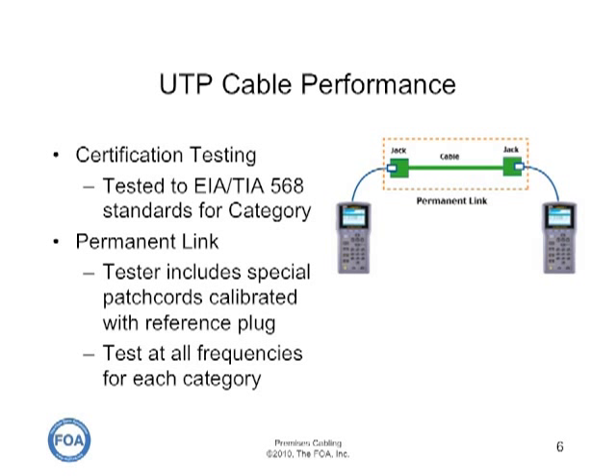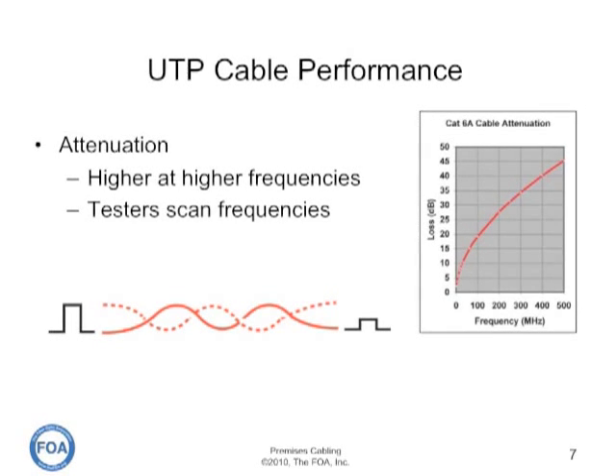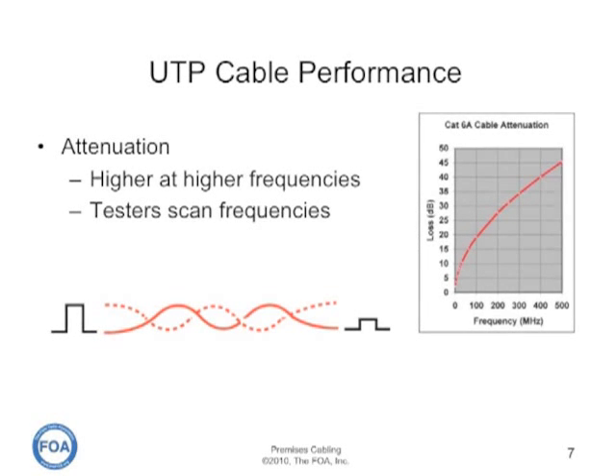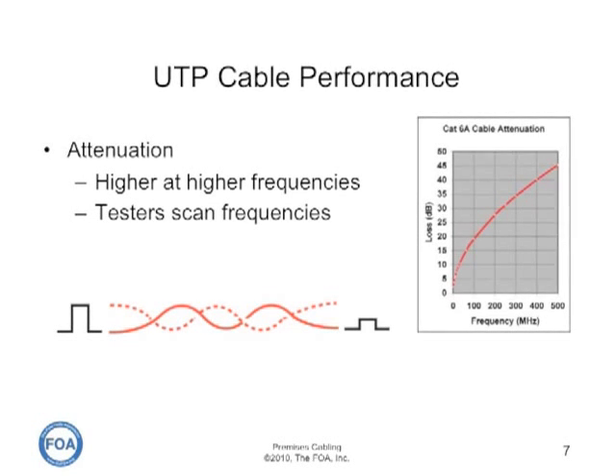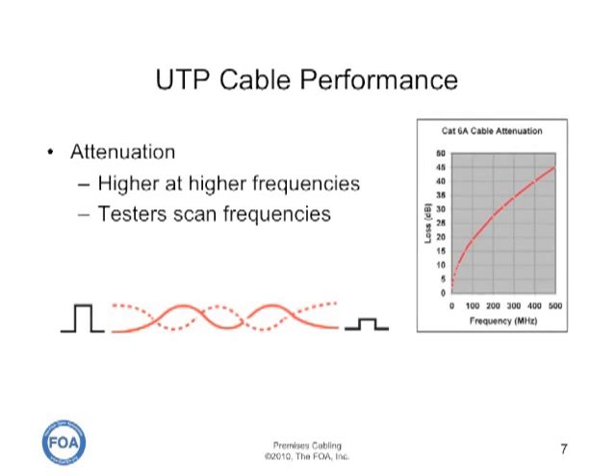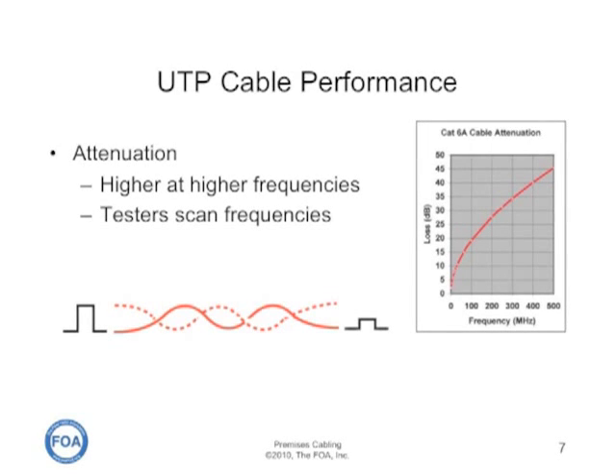Certification of the installed cable, what's called the permanent link, has to be done according to industry standards, and the standards are different for each category of cable. The permanent link includes all of the installed cable and is typically tested from the jack at the patch panel to a jack at a work area outlet. The tester includes special patch cords calibrated with a reference plug, and they test at all the frequencies required for each category. The attenuation of the cable plant is tested as the tester sweeps through the frequencies over which the cable is specified to run according to its category rating. Attenuation is higher at higher frequencies, so the testers test at multiple frequencies to see if the cable plant meets the industry standards at all specified frequencies.